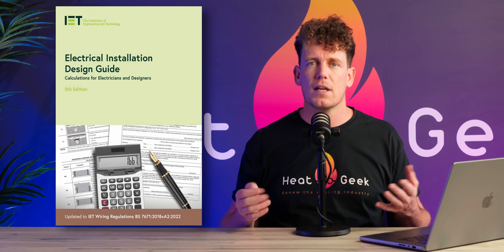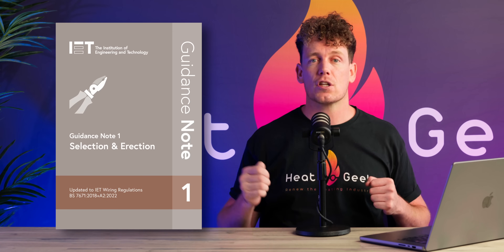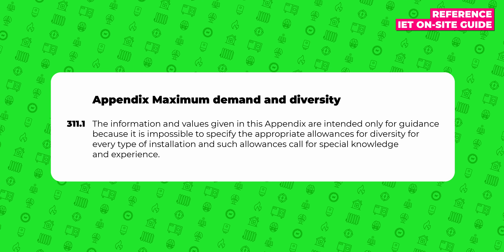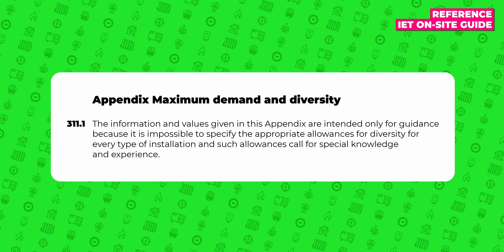Essentially there are three guidance books in the UK on Maximum Demand: the Electrical Installation Design Guide, the On-Site Guide, and the affectionately titled Guidance Note 1 Selection & Erection. These all essentially contain exactly the same information, which is not surprising as they're all produced by the Institute of Engineering and Technology. The opening paragraphs on Maximum Demand say the information and values given in this appendix are intended only for guidance, because it's impossible to specify the appropriate allowances for diversity for every type of installation, and such allowances call for specialist knowledge and experience. I then went on to read the least helpful guidance I've ever come across.